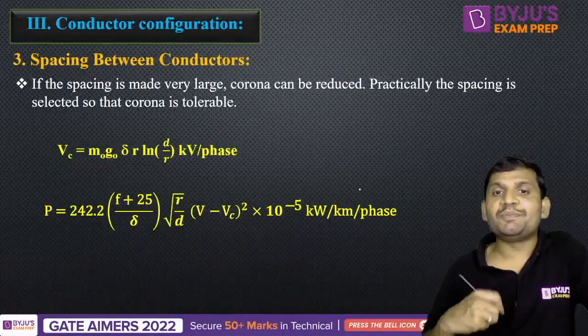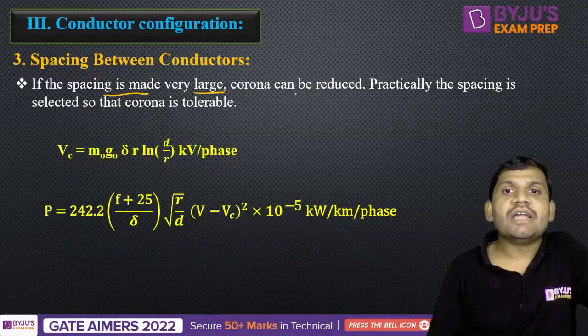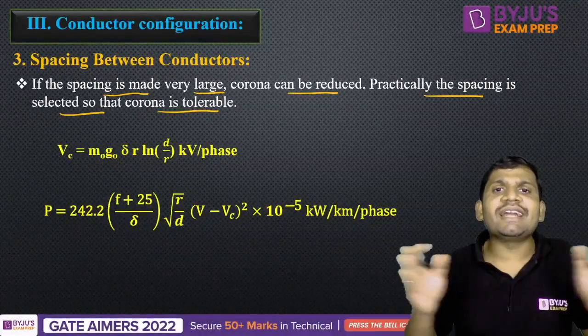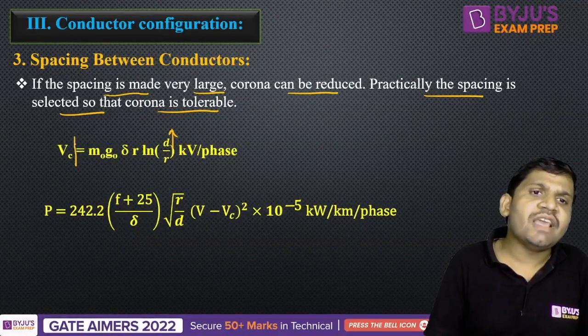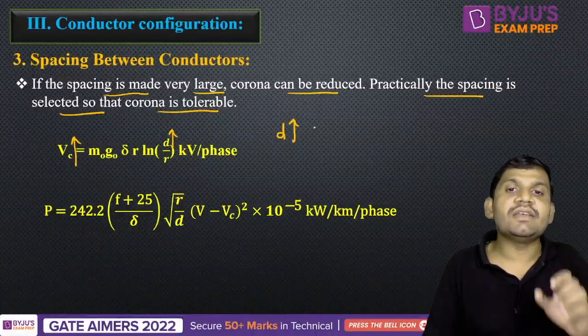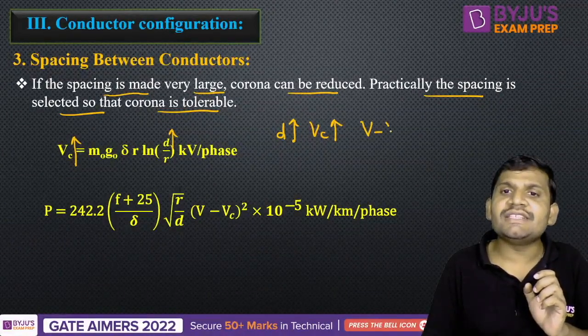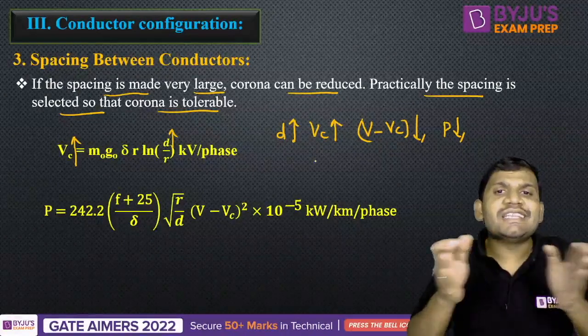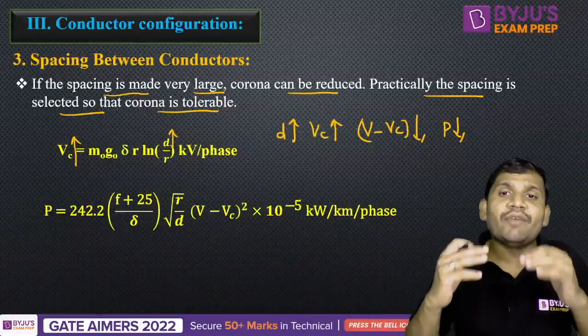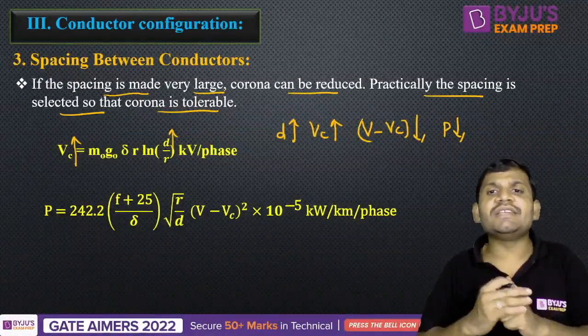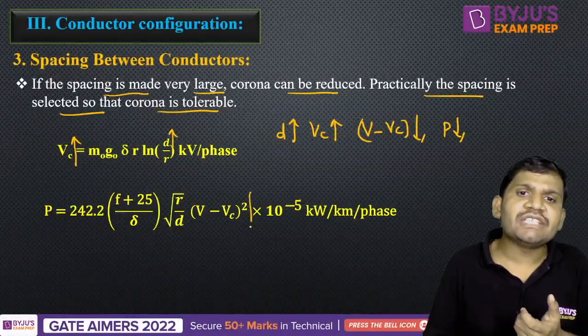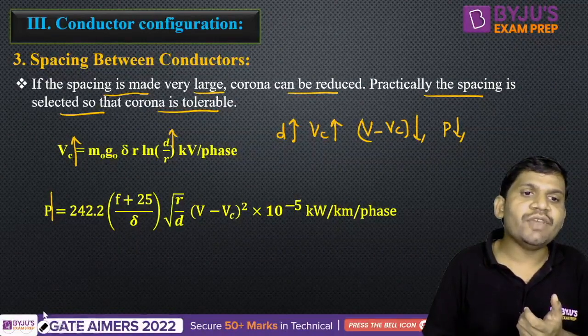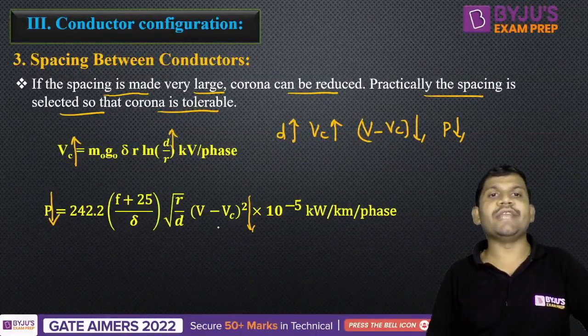One more point: the spacing between conductors. If the spacing is made very large, corona can be reduced. Practically, spacing is selected so that corona is tolerable, but this is a costly method. If the distance between conductors D increases, then Vc also increases. Once Vc increases, V minus Vc reduces, then corona loss reduces. However, increasing conductor spacing increases cross-arm length, tower size, and cost.